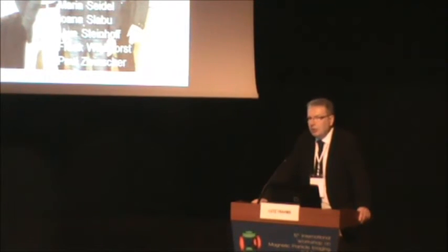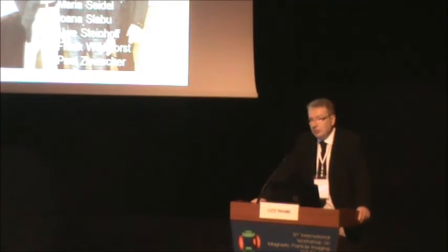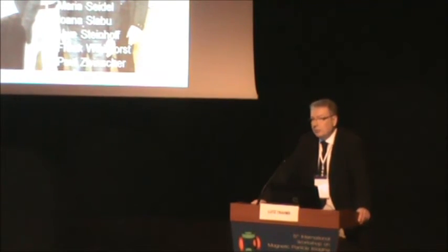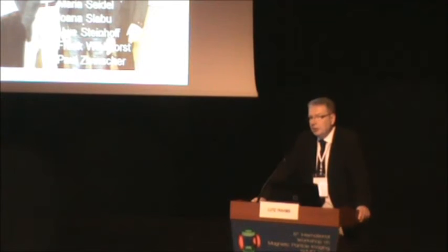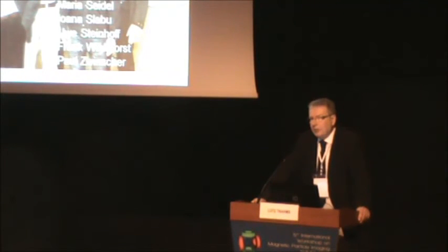Well, if you're talking about MPI, then at present at least we are in the range of 25 kilohertz or even 150 kilohertz or so. In that case, RF coils are absolutely the right device for the recording. But on the other hand, it might also be useful to turn down the frequency of MPI to lower frequencies to avoid a couple of problems that may come up in terms of heating up the tissue, and other problems.